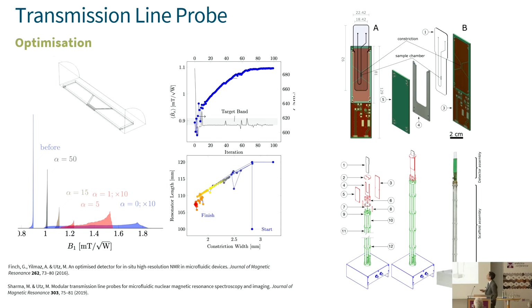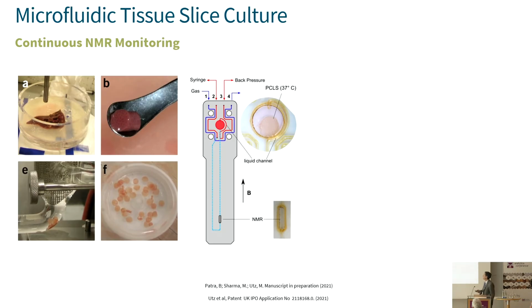We did some topology optimization to find the right shape for the strip line and the sample chamber simultaneously, and that gave us the best compromise between homogeneity of the B1 field and probe efficiency. And that then allowed us to get these spectra. I'll talk about sensitivity a little bit later.